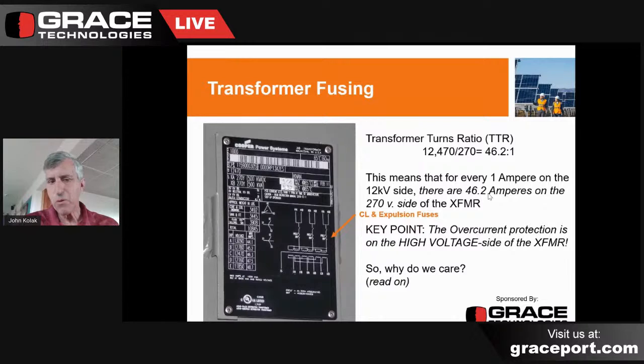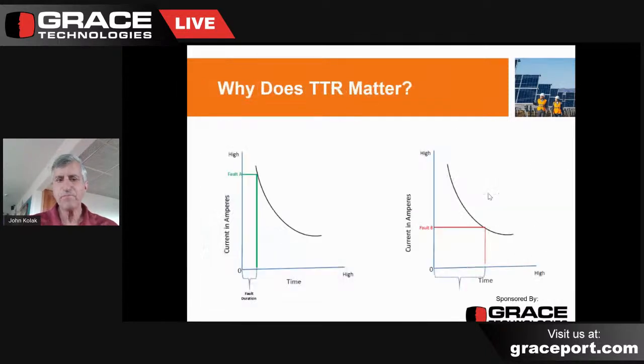So this means that for every 1 amp you have on the 34.5 side of that, the 12 kV side of the transformer, you would have 46 amps on the low voltage winding. And this is very important from an arc flash calculation. So why do we care? Well, let's take a look.